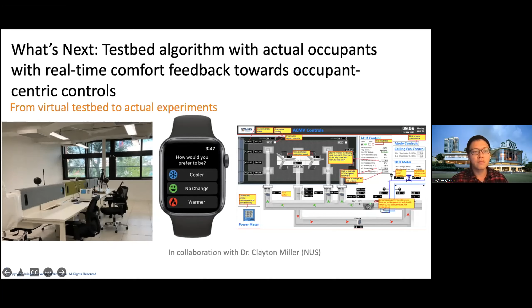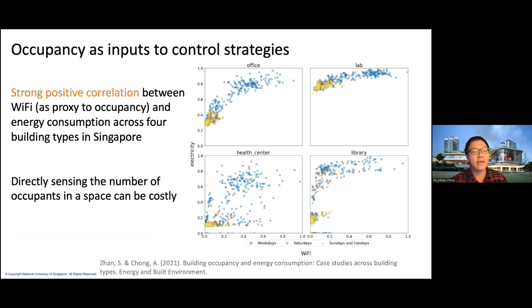Moving on to occupancy, which is also key to control strategies. We previously found a strong positive correlation between Wi-Fi, a proxy for occupancy, and energy consumption across 4 different building types. However, directly sensing the number of occupants in a space can be costly. This is particularly important in Singapore, where fresh air provision can be very expensive and significantly increase cooling load due to high outdoor humidity.